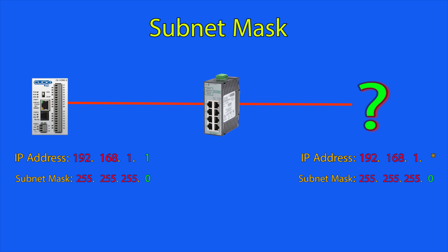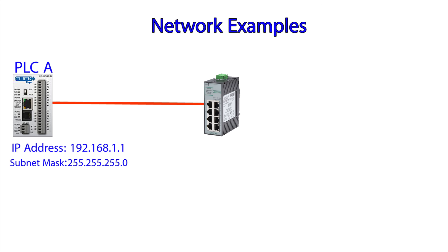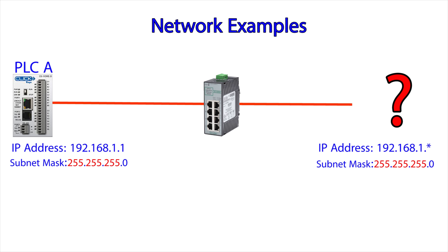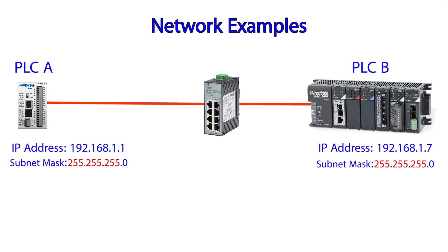Let's see some examples to make this point clear. So we have PLC A. We can see that the first three octets of the subnet mask are 255 and the last is 0. This means that any device wanting to communicate with this PLC would need to be 192.168.1.something. Now let's add in PLC B to our switch. Will these two devices be able to talk? Yes — the first three number groups of the IP addresses match and the last is different.